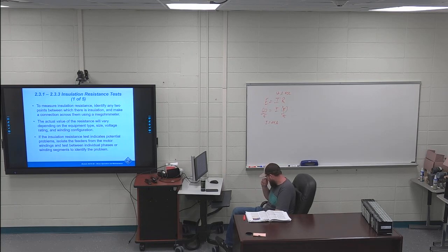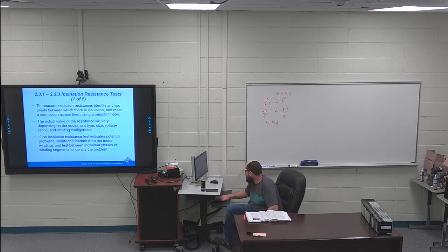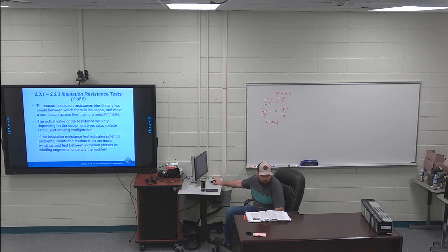Voltage is going to heat up a cable. The hotter a cable is, normally the less resistance it has. So it's seeing what the... hold on. I got that backwards. The resistance goes up after it's been heated up in insulation that is good. That's what it is. So you want your number to be higher.